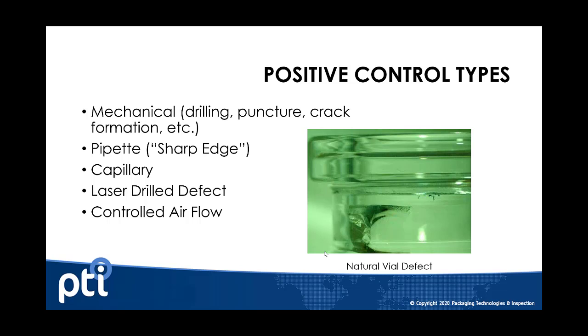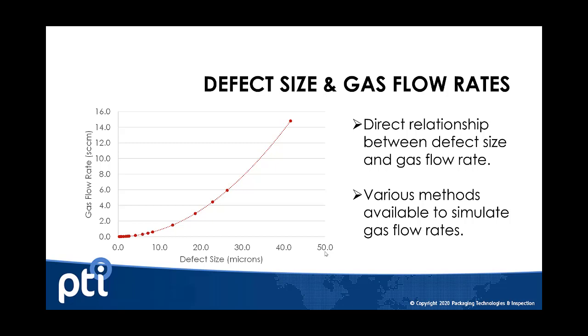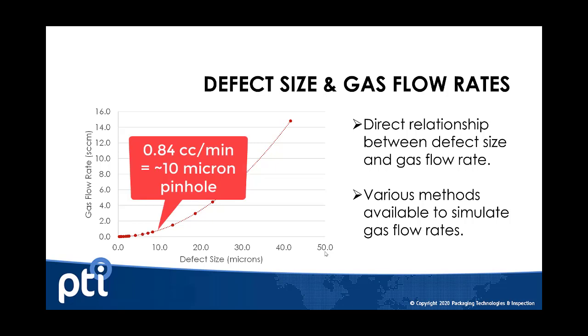If we have to create defects that are smaller than 10 microns, there are certainly other ways that we can simulate or create that effect. A pipette is one way, constricting the flow similar to the capillary. More common methods include a laser drilled defect, which is a certified type defect, or you can introduce a flow meter to simulate the leak. A defect size is correlated to a gas flow rate, so for a vacuum-based leak test method, a 0.84 cc per minute flow rate can simulate a 10 micron defect.